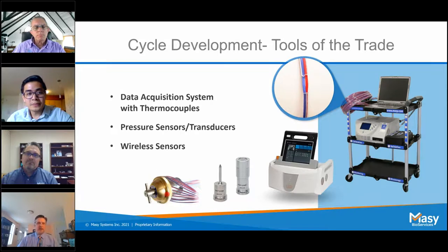Yep, there you go. Back for OQ for being able to ingress your thermocouples. So this is certainly a feed through port. A lot of sterilizers do have a port that has a sanitary connection. Fear not, if it doesn't have a sanitary connection, usually there's other ways that we can get in there and be able to hook up contraptions such as this or something similar.